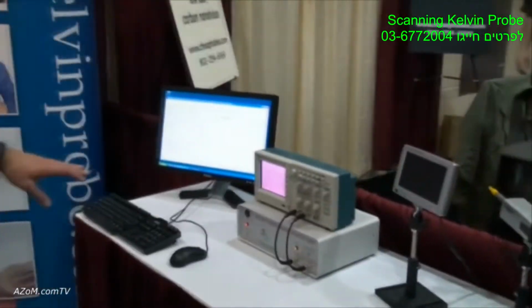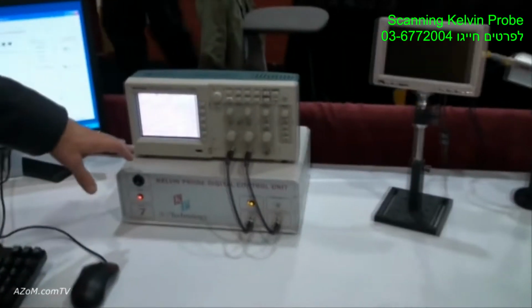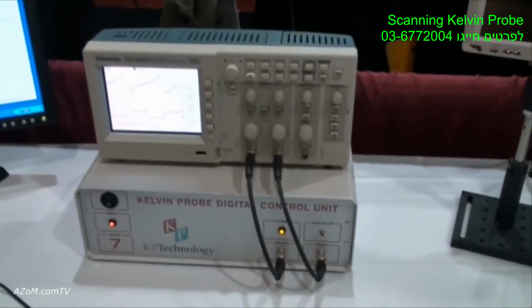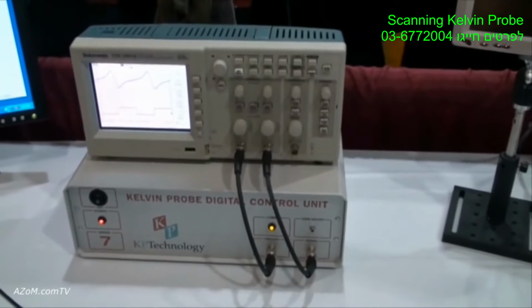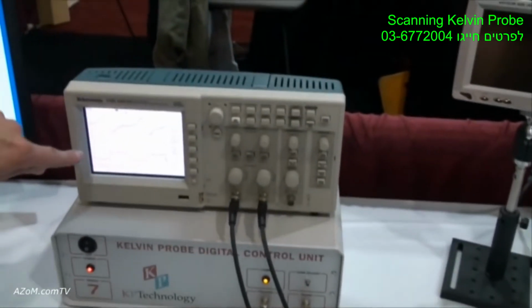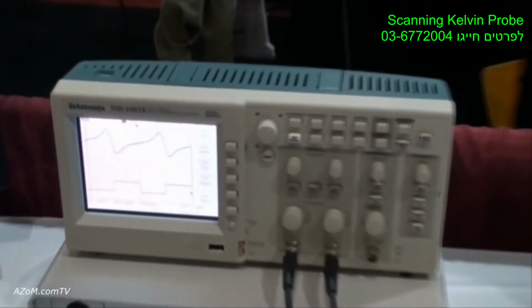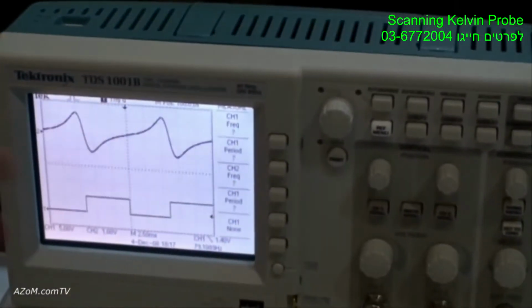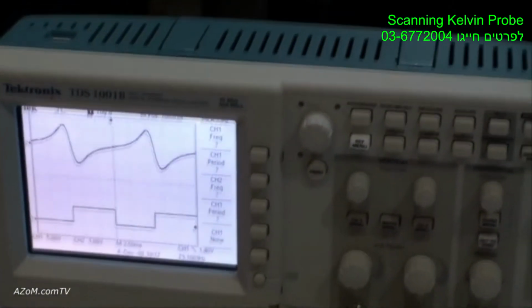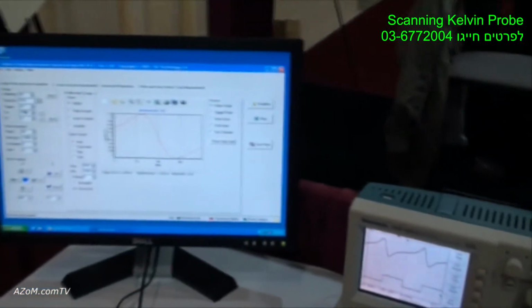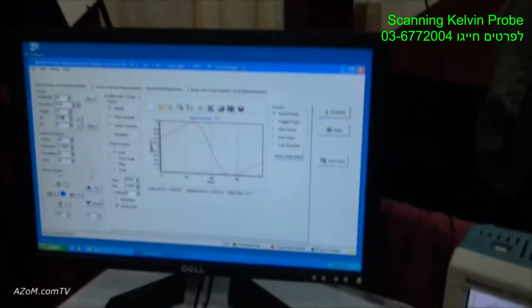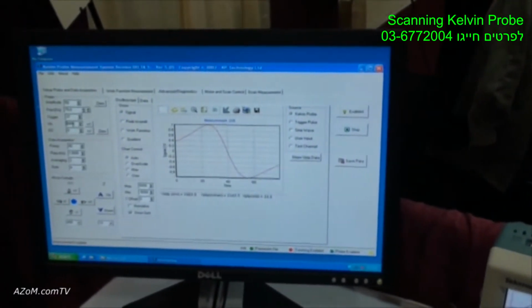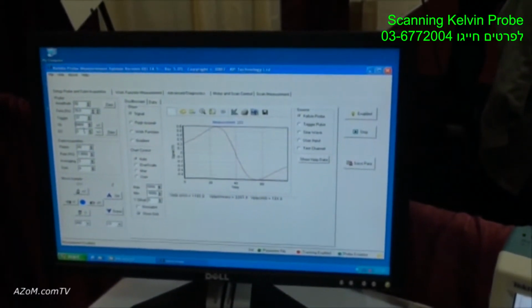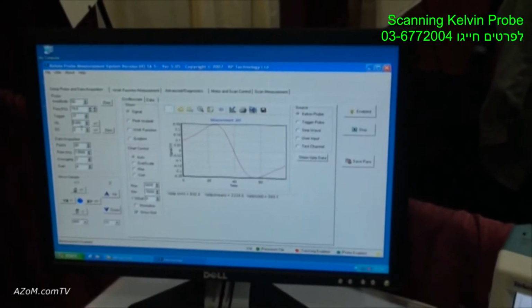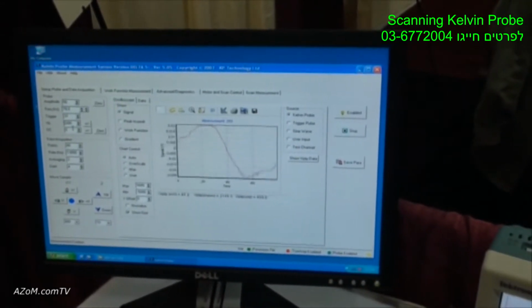This is a control unit. It's digital. It drives the probe. It sets the frequency of the probe, the amplitude of oscillation, and the spacing. And this is the Kelvin probe signal. This is the closest approach as the tip comes close to the sample, and this is the point where you go farther away. We control the tip potential. In the Kelvin probe measurement, if I control the tip potential, I can make the energy of the tip and the surface the same, and at that point I'll get zero signal. That's called the null field.